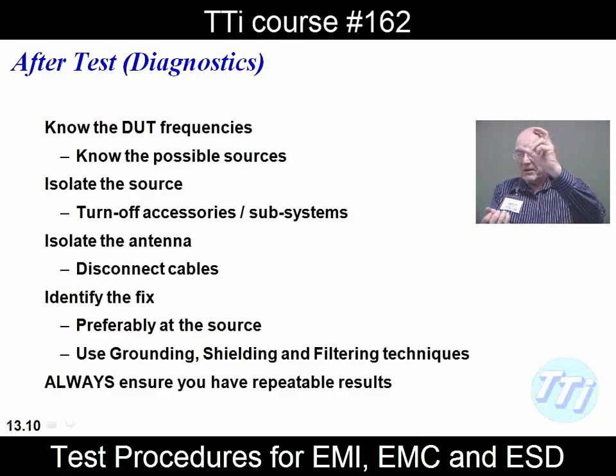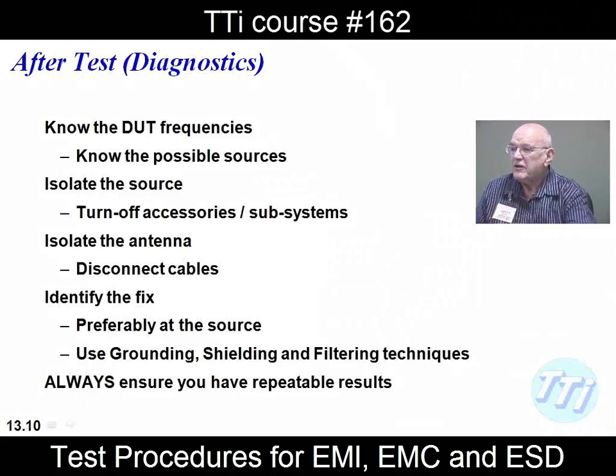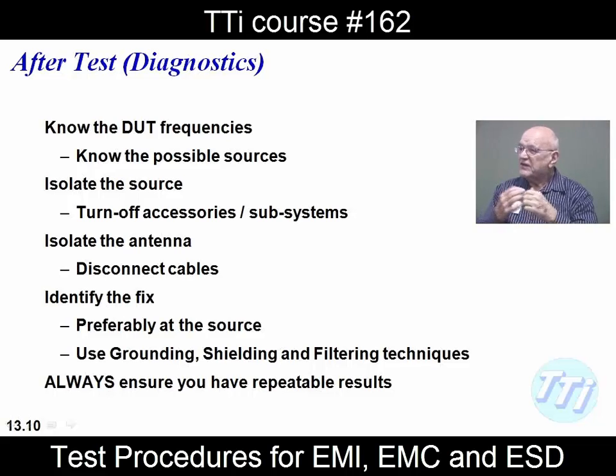You actually open it up, put it around the actual cable, and you checked it all the way down. You checked every one of the cables. You made a change. So then you did the same thing. So this is kind of like the same idea. Be able to isolate that. And hopefully you fix the thing at the source rather than creating a situation where you're acting as a Band-Aid.